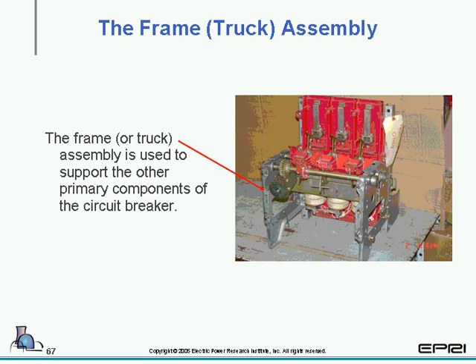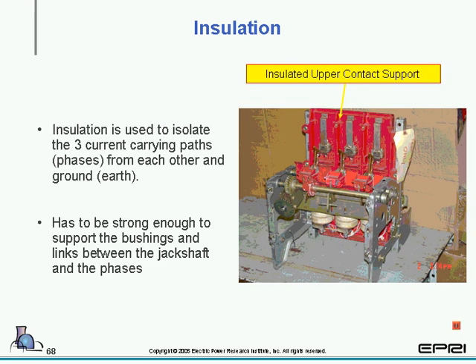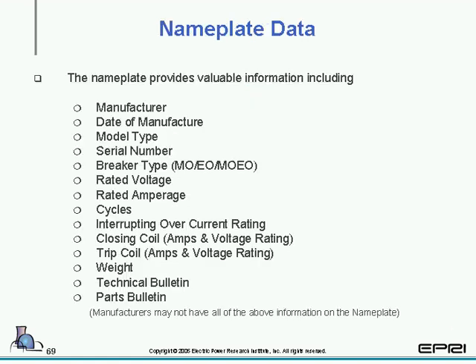The next one we'll take a look at is the frame or truck assembly. The frame or truck assembly is used to support the other primary components of the circuit breaker. Normally it's made of metal. The insulation. The insulation is used to isolate the three current carrying poles or phases from each other and ground. A key note, it has to be strong enough to support the bushings, links between the jack shaft and the phases.